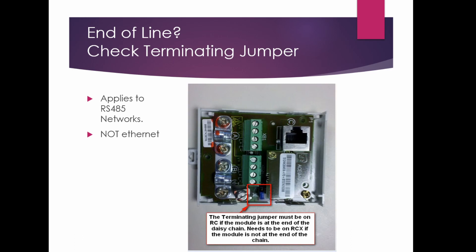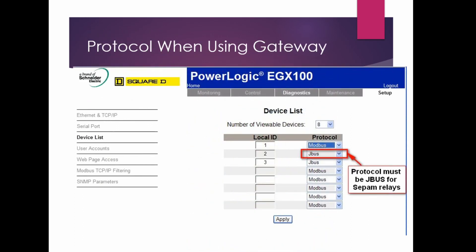If the module is at the end of the line, make sure the RC and RCX jumper is in the proper position. This does not apply to Ethernet — only to daisy-chained RS-485. Your protocol when using a gateway, whether it be the EGX 100, EGX 300, a Lynx, or an ION meter COM port, has to be set as JBUS in order to have the proper offset.